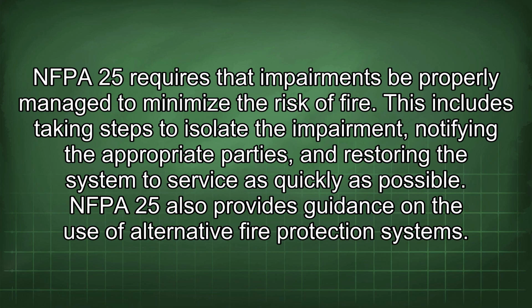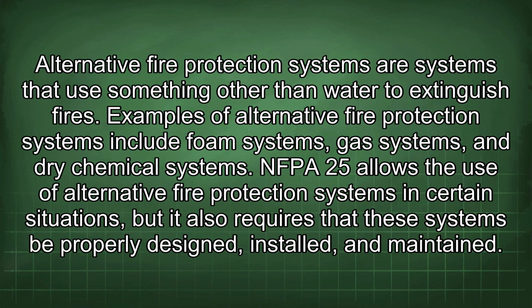This includes taking steps to isolate the impairment, notifying the appropriate parties, and restoring the system to service as quickly as possible. NFPA 25 also provides guidance on the use of alternative fire protection systems. Alternative fire protection systems are systems that use something other than water to extinguish fires. Examples include foam systems, gas systems, and dry chemical systems. NFPA 25 allows the use of alternative fire protection systems in certain situations, but it also requires that these systems be properly designed, installed, and maintained.